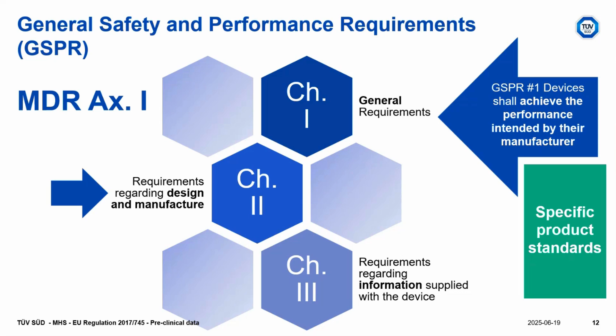So I will now do a short overview of chapter 2 of the GSPR, just to give you some highlights on the notified body's attention. First, GSPR 10, which is very big and complex, and is one of the GSPRs that had major changes from the previous essential requirements of the MDD. It is the section regarding materials, where the source of the requirements in Annex 2 is the definition of all the materials in direct and indirect contact. So we first need to have, in the technical documentation, a very well detailed assessment of all the materials composing the device.